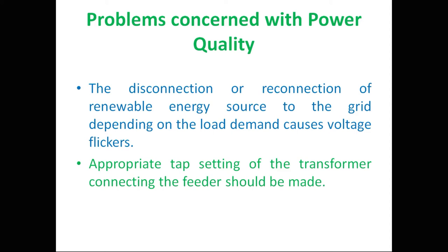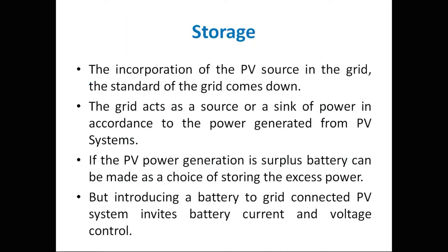The solution for voltage flicker is appropriate tap setting of the transformer connecting the feeder. By setting the transformer tap properly, we can reduce the voltage flicker. Since voltage flicker is a matter of magnitude, we can reduce or increase it using transformers. So the two power quality problems are harmonics and voltage flickers.